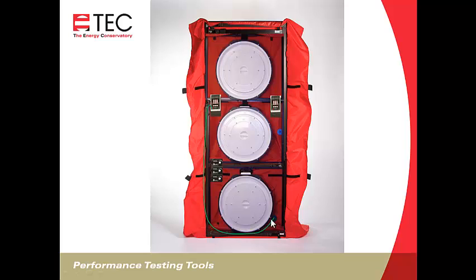It's a double-sided tap. You can see there's a blue one up here, there's a green one at the bottom, and you'll connect the tubing to that. And then on the outside, you'll connect a long tube to that and run it. Typically you'll run it to the center of that side of the building. And then the second tube, channel B, will connect to the lower fan.